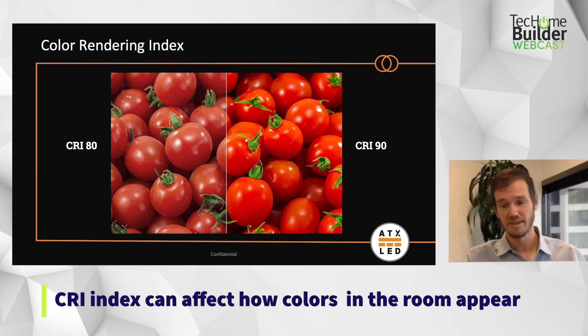What about the color of the light and the tuning of the light and how it impacts what you see in the space? On all LEDs, there's a rating called CRI, which stands for Color Rendering Index. LEDs naturally aren't very good at reproducing reds — that's the downfall of especially inexpensive, low quality LEDs. The higher the CRI number, the better and more realistic the colors are going to appear compared to natural light. A lot of LEDs on the market, especially in the early days, were around CRI 80, and everything looks very flat. If you had a red tablecloth, it would appear much more black. Red fruits and tomatoes are a classic example.